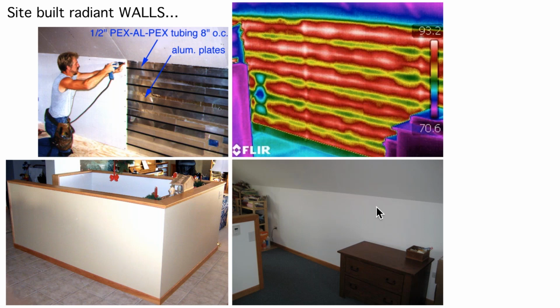And you can see here's the fellow putting the drywall screws in. You can actually see that the screws are going in halfway between the tubes, so that the screws don't even go through the aluminum plate. They basically just go through the drywall, the foam, and then they draw up tight against that 7/16 oriented strand board that is behind the foam. Here's a thermal image of that wall when it's operating, and here's what it looks like when it's all finished. I mean, visually, you have no idea that it's a heated surface. But the red here again is indicating that those plates are doing a good job spreading that heat out.